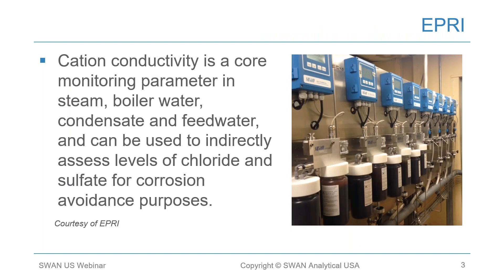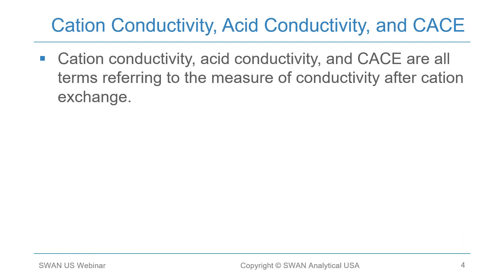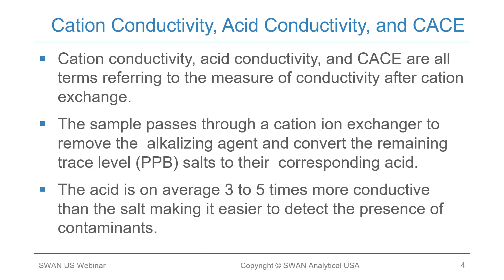Good morning everyone. We're very excited to have you join us for this webinar. We're going to be discussing a better way to measure cation conductivity. According to EPRI, cation conductivity is a core monitoring parameter for steam, boiler water, condensate, and feed water, and can be used to indirectly assess the levels of chlorides and sulfates present for corrosion avoidance purposes. Cation conductivity, acid conductivity, and CACE are all terms referring to the measurement of conductivity after cation exchange. The sample passes through a cation ion exchanger to remove the alkalizing agent and convert the remaining trace PPB-level salts to their corresponding acid, which is on average three to five times more conductive than the salt, making it much easier to detect the presence of contaminants.